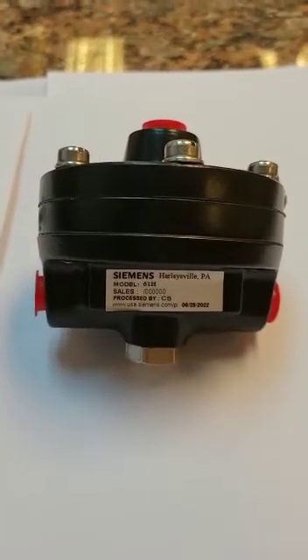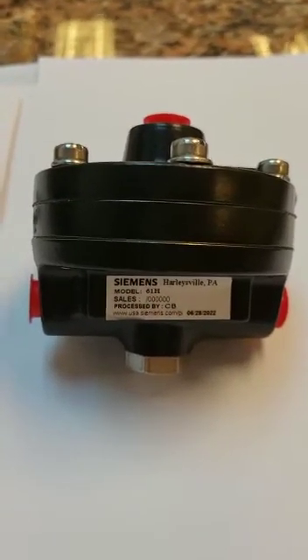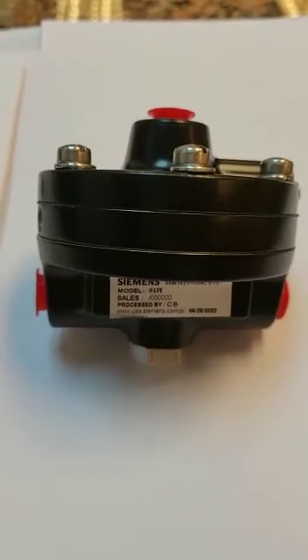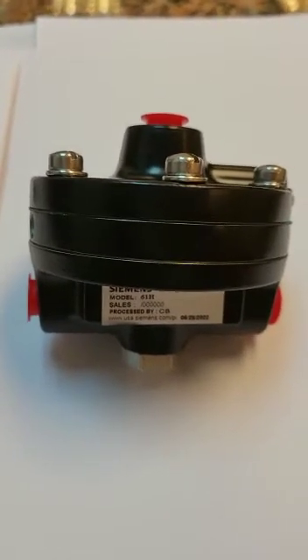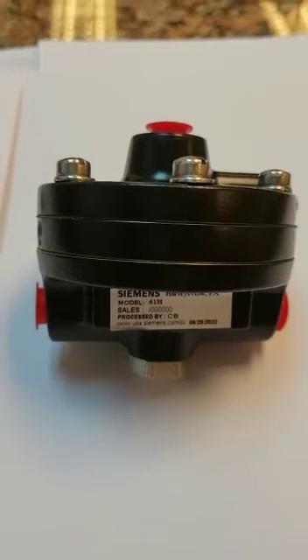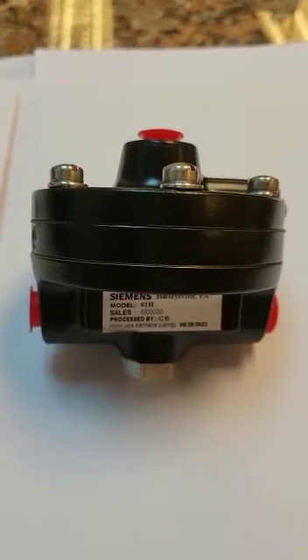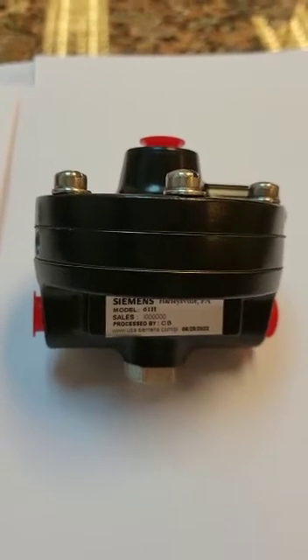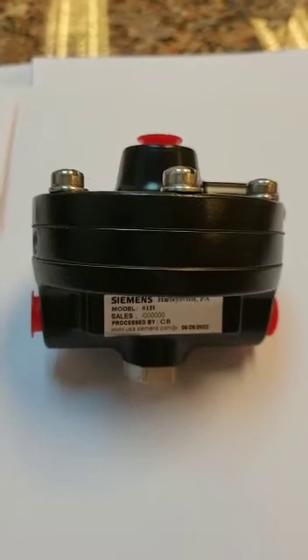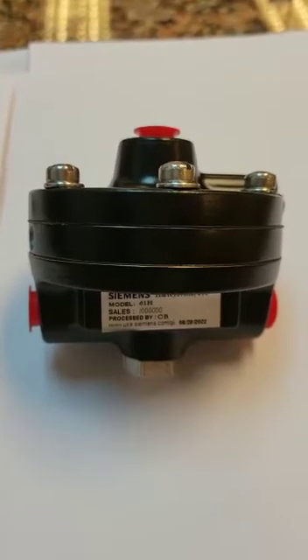When do you use this Booster Relay? When you supply a valve positioner to a customer, the valve positioner will provide 3 to 15 PSI output to control the valve opening and closing. Sometimes the 3 to 15 PSI output from the pneumatic positioner — I emphasize: the volume of the airflow, not the pressure — the pressure of 3 to 15 is always the same. The airflow can be big or can be small.